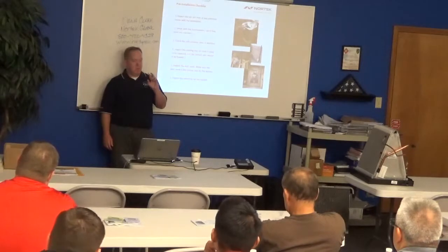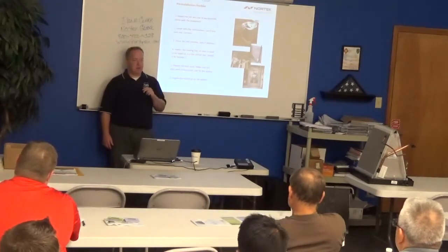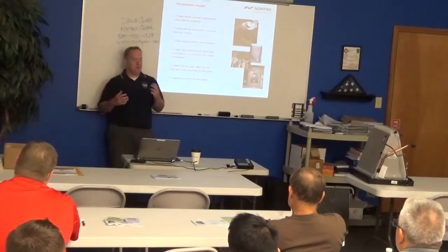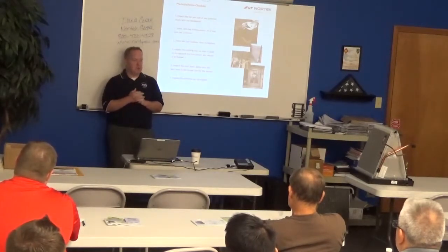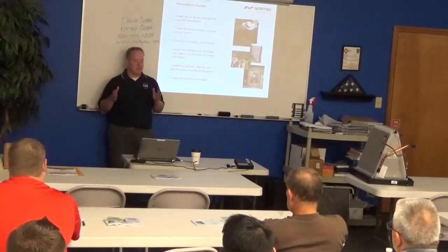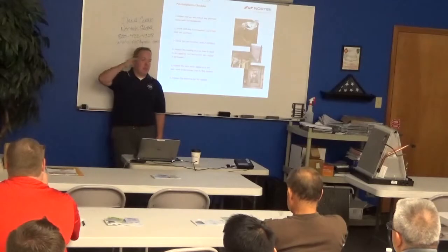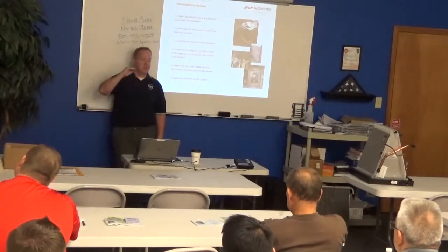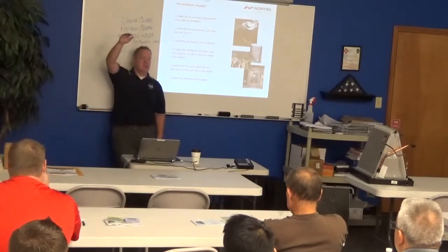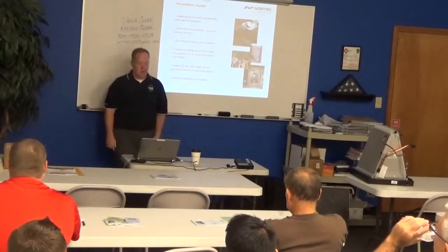There is nothing more difficult, nothing more deflating than having to come in on somebody else's job, when you didn't do the install, when you get that impression, when you show up and have a sneaking suspicion we may have been the third or the fourth company contacted on this situation. That's that moment right then and there where you have to basically say, if this is going to be my system that I have to inherit, I'm not going to start at the top, I'm going to start at the base of that pyramid. I'm going to start with some of the fundamentals, because if they've been having this frequency of issues with this thing, and they're that frustrated, I'm not going to start at the top and try to work my way backwards through it. I'm going to start with the fundamentals. I'm going to look at the layout on the piping for the line set, things like that.